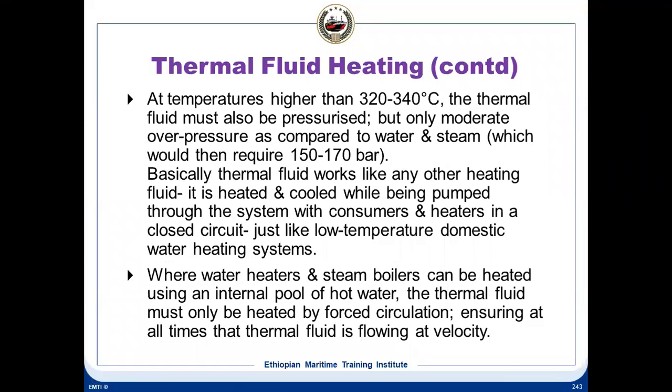At temperatures higher than 320 to 340 degrees centigrade, the thermal fluid must also be pressurized, but only a moderate amount of overpressurization above atmospheric is required as compared to water or steam, which would require 150 to 170 bar. Now we are just going from 300 to 340.